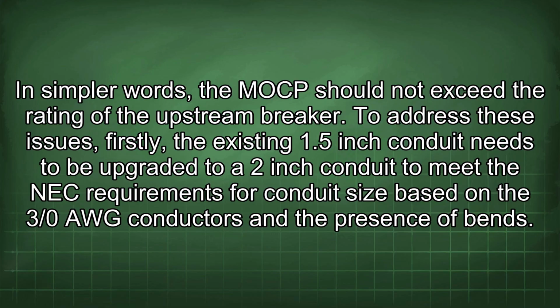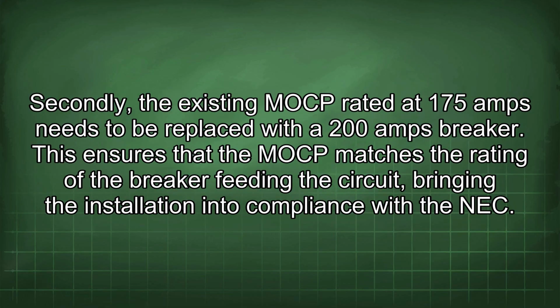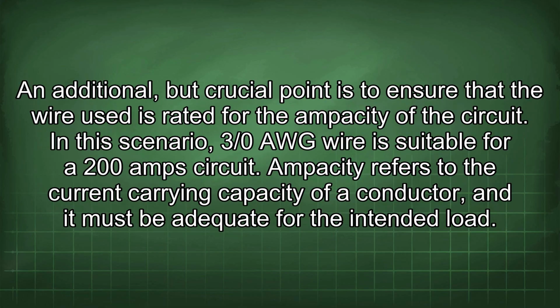To address these issues, firstly, the existing 1.5-inch conduit needs to be upgraded to a 2-inch conduit to meet the NEC requirements for conduit size based on the 3/0 AWG conductors and the presence of bends. Secondly, the existing MOCP rated at 175 amps needs to be replaced with a 200 amps breaker. This ensures that the MOCP matches the rating of the breaker feeding the circuit, bringing the installation into compliance with the NEC. An additional but crucial point is to ensure that the wire used is rated for the ampacity of the circuit. In this scenario, 3/0 AWG wire is suitable for a 200 amp circuit.